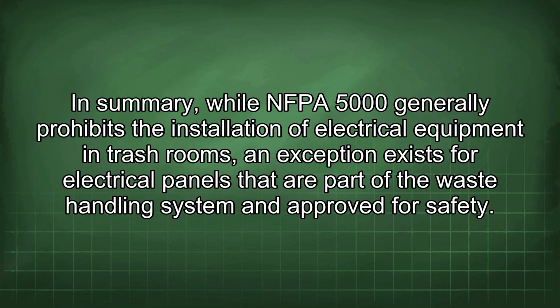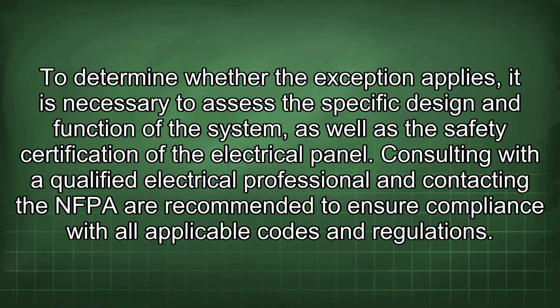In summary, while NFPA 5000 generally prohibits the installation of electrical equipment in trash rooms, an exception exists for electrical panels that are part of the waste handling system and approved for safety. To determine whether the exception applies, it is necessary to assess the specific design and function of the system, as well as the safety certification of the electrical panel.